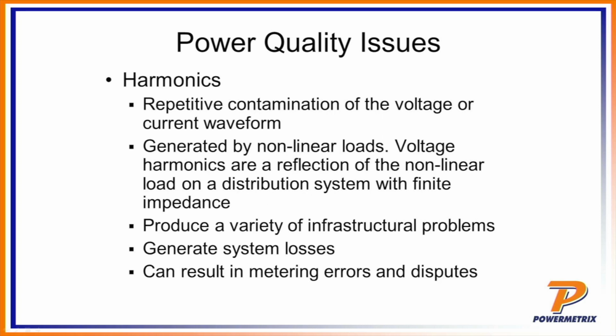Moving on to the next issue, harmonics. Harmonics is defined as a repetitive contamination of voltage and current waveform. If we break that down a little bit further, the first word there that's really important is repetitive, meaning that a harmonic waveform is something that happens over and over again, pretty much every cycle or every few cycles. That's to be distinguished from a sag or a swell, which may be, once again, based on load and vary over the course of a day. It's very different from a transient kind of thing, like a lightning strike, which may happen very intermittently.